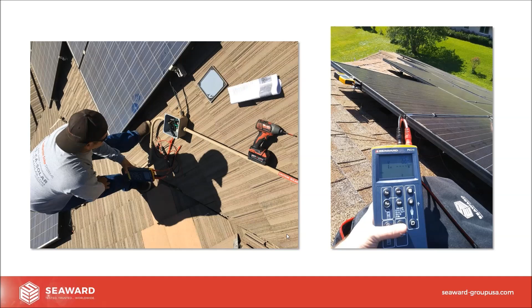Carrying on that theme, we can make a connection up at the J box. And again, when I say make a connection, that enables us to take open circuit voltage, short circuit current, insulation resistance, an IV curve trace, the irradiance, and the cell temperature with ambient temperature, all with one push of a button taking about 30 seconds. So we can do that at the inverter as shown or at the J-box. Also, we can do it at a panel level.